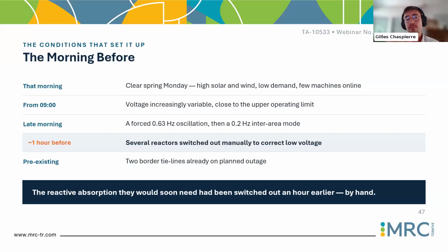On top of that, in the late morning, they start seeing oscillations coming from first converters, then from a well-known inter-area mode between Spain and the rest of Europe. Then, as always, it's not new. The operators follow the book, and the mitigation means that they need to apply facing these oscillations. They were reducing the flux, the export of power from Spain to the rest of Europe, which decreased the angle difference and damped the inter-area mode. But more importantly, they have disconnected a lot of shunt reactors.